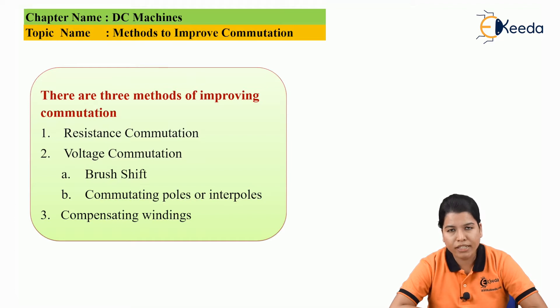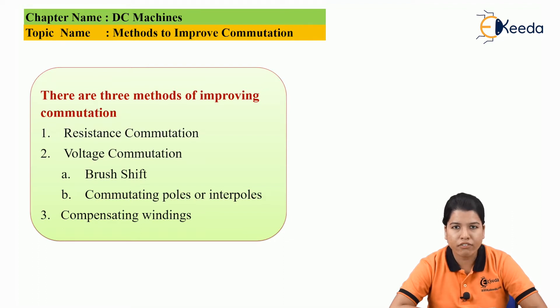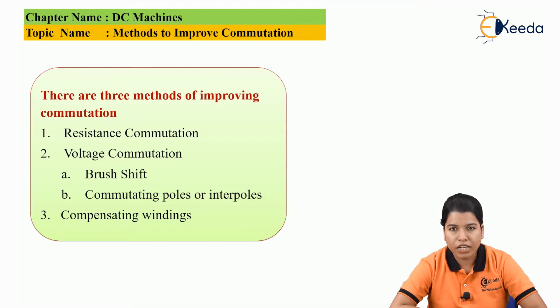There are two methods by which this can be done. The first is by brush shift. In brush shift, when armature reaction takes place, the total flux gets distorted. The MNA has the tendency to remain perpendicular to the resultant flux. Hence, according to the distortion of the resultant flux, the magnetically neutral axis rotates. Since the brushes are always placed on the MNA, as per the rotation of the magnetically neutral axis, the brush also rotates.